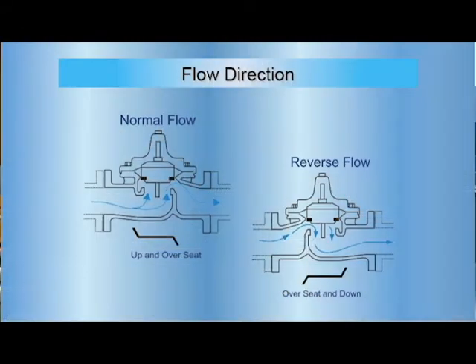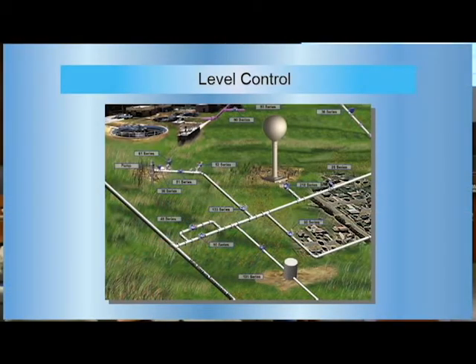For flow direction, most of the time you're going to see normal flow — up and over the seat — but they do have reverse flows. Basically, with a normal flow, when it fails it's going to fail in the open position. If you want to fail in the closed position, that's where you go with reverse flow. It's not as common but there are situations where that's warranted.